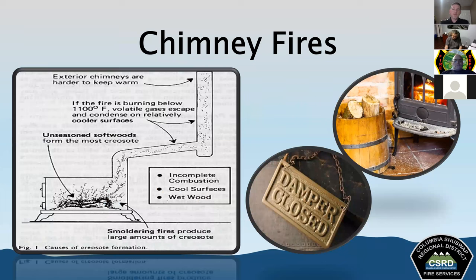So restrictions in air supply in chimneys are a result of poor ventilation, and that occurs when the glass doors are closed and the damper is not opened wide enough to let the byproducts travel rapidly up the chimney and be expelled from the house, right? In wood stoves, the restrictions are caused by closing the stove damper or the air inlets too soon and too often. There are other factors that can lead to creosote buildup, like failure to maintain a proper temperature inside the flue.